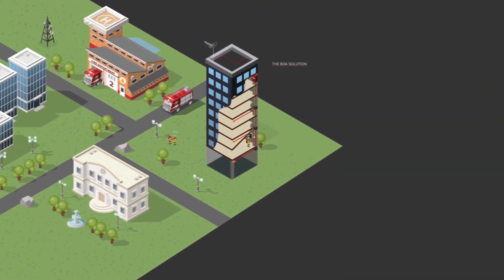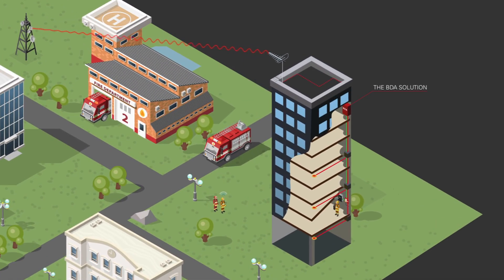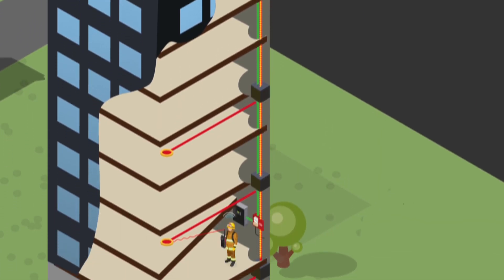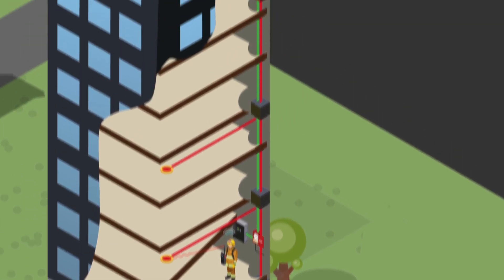Our emergency radio communication enhancement system can provide 100% in-building coverage. It achieves this by boosting signals from the public safety radio repeater with a bi-directional amplifier, also known as BDA in the life safety industry, and distributes it throughout the building using the distributed antenna system. The BDA receives and amplifies transmissions from radios inside to the repeater antenna outside, safeguarding reliable two-way communications.